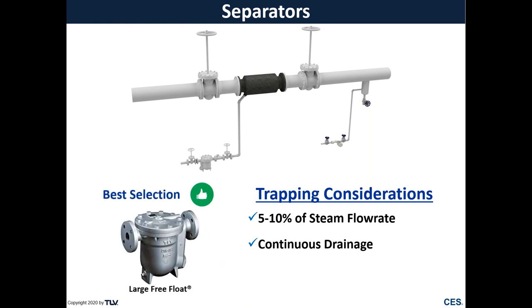So typically we're going to see a large free float style trap on a separator. Now often we see a large separator in a line trying to be drained by a half inch small disc trap, which often doesn't have nearly enough capacity in order to drain the amount of entrained moisture. So it's important to really consider steam trap sizing with that separator.